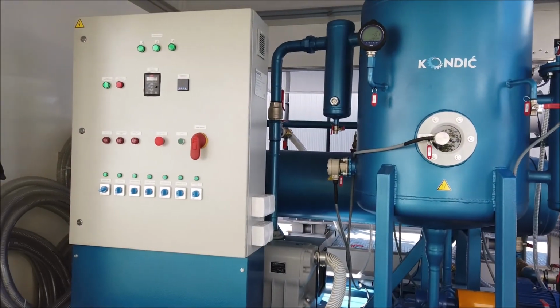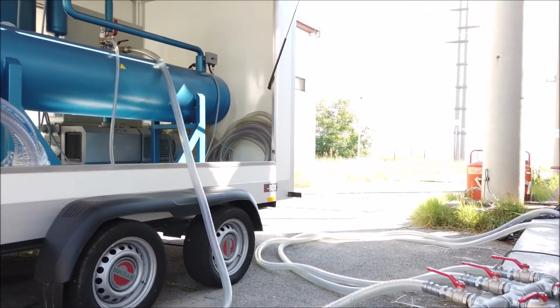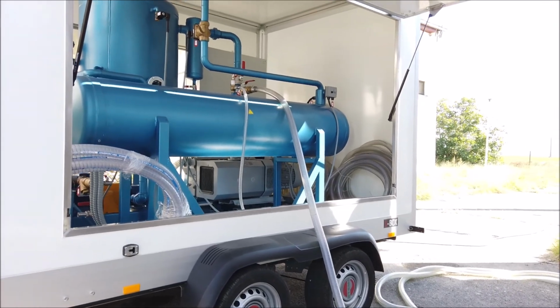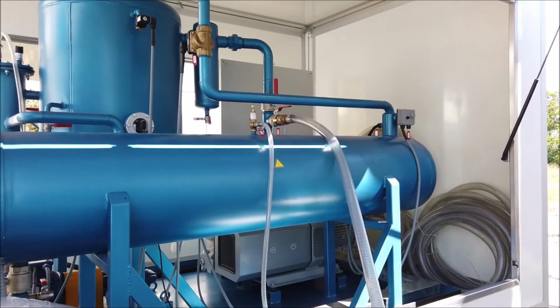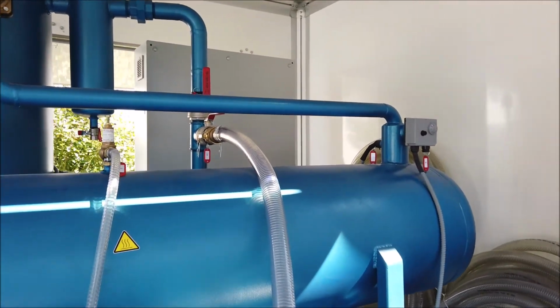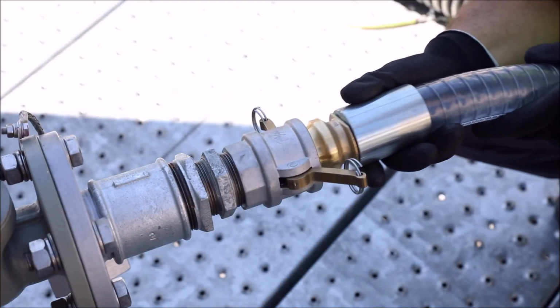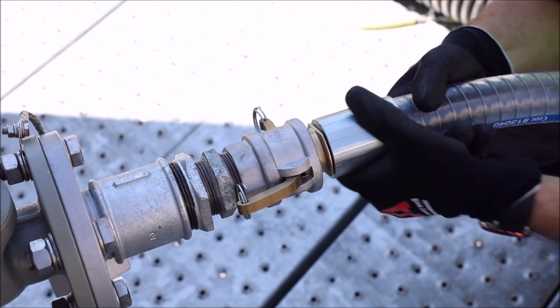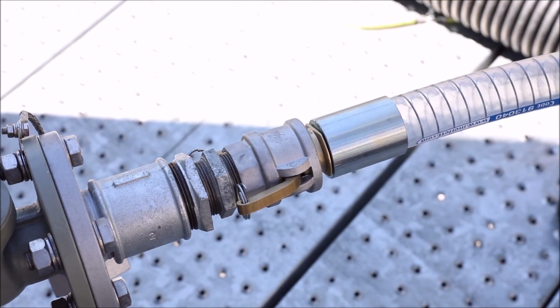Oil should be filtered with the vacuum oil treatment device by simple oil circulation. The total quantity of oil must circulate three times through the vacuum oil treatment device. After the transformer has been filled with oil and it was inactive for a day, it should be vented.